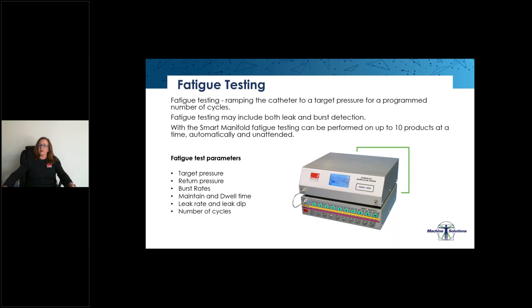ISO 10555 Annex B provides us with a good example of a simple fatigue test. The standard calls for a balloon to be pressurized to its rated burst pressure and maintain there for 30 seconds for a total of nine cycles. Our target pressure in this example would be the rated burst pressure, our return pressure would most likely be zero, and our maintain time is 30 seconds.